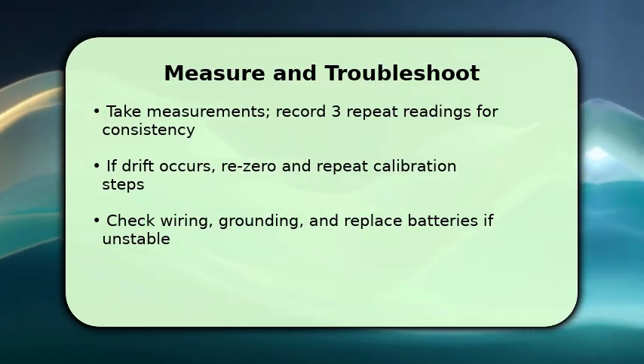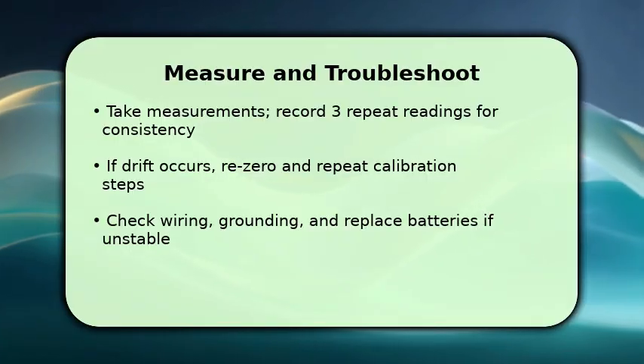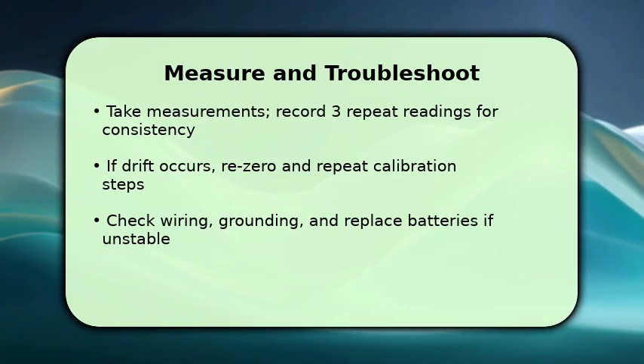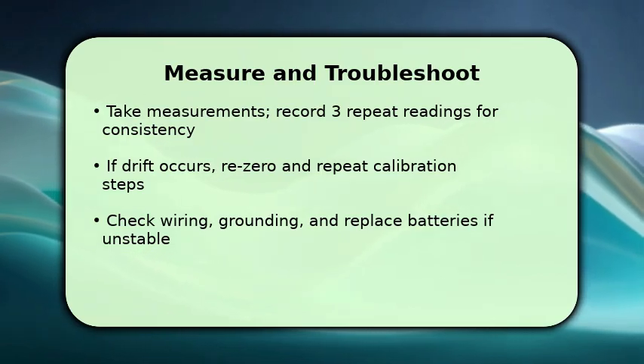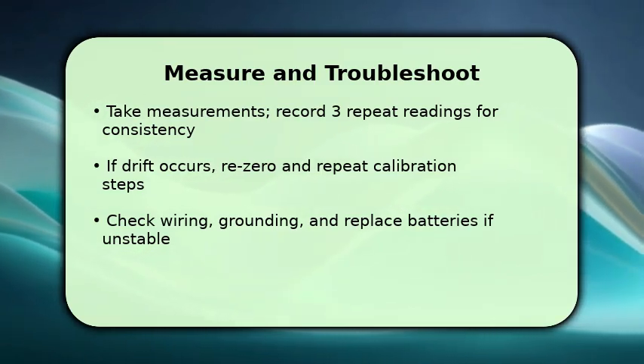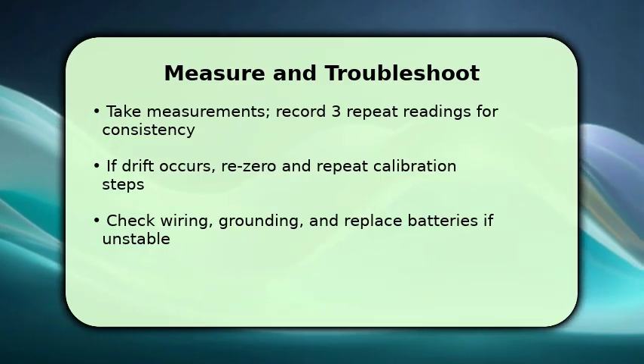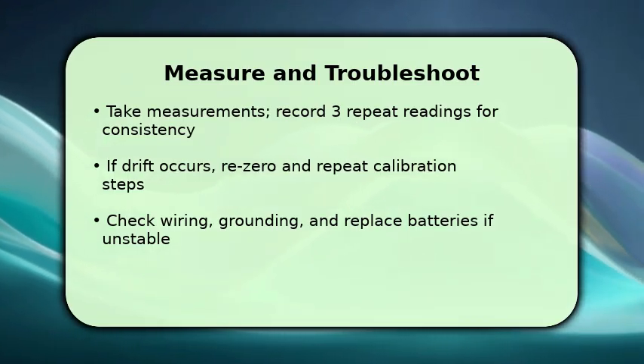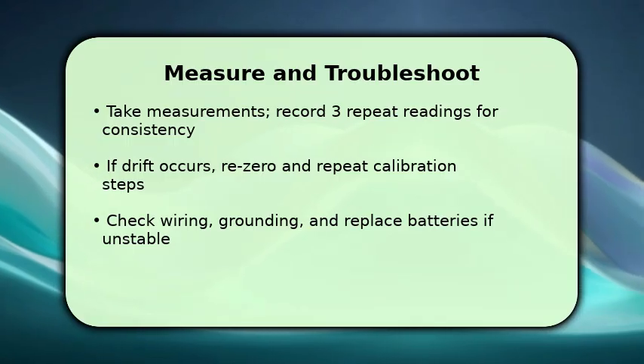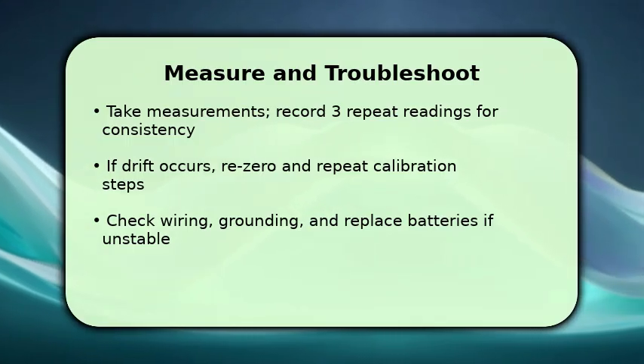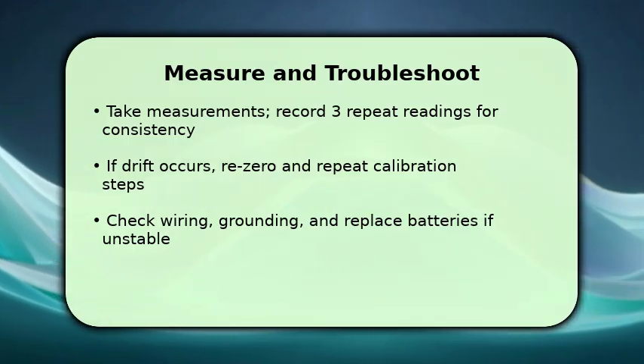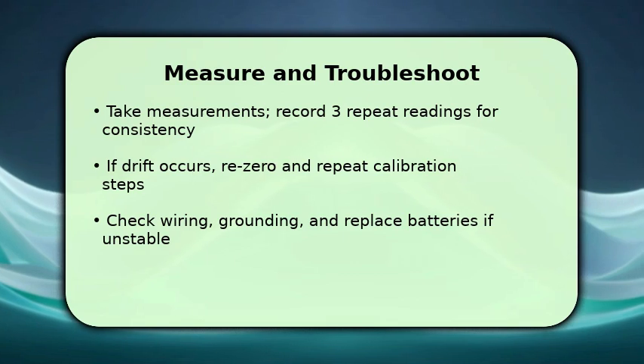If you notice drift or readings that jump, re-zero immediately, and if unresolved, repeat the calibration routine. Make sure to check wiring, grounding, and probe connections. Intermittent contacts mimic sensor faults. If instability persists, replace batteries or swap to a regulated supply. This often solves power-related errors and restores reliable output.